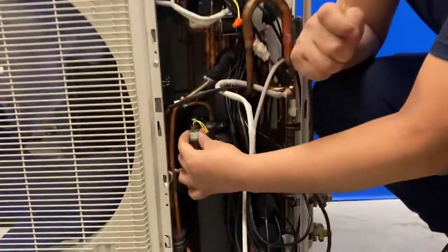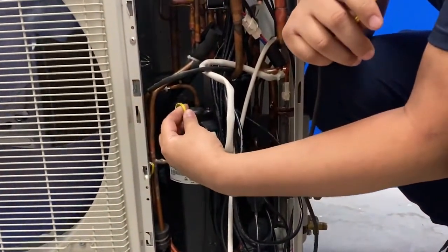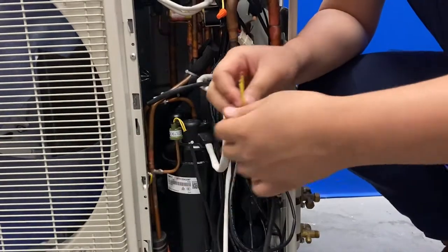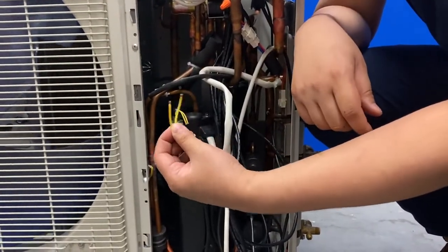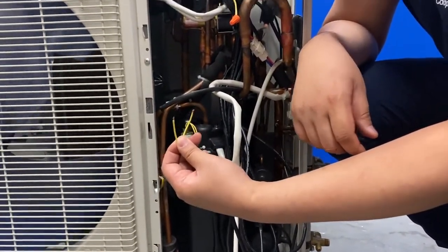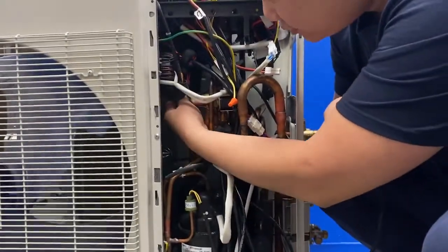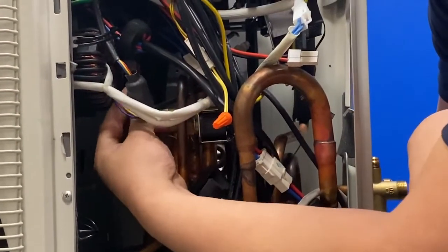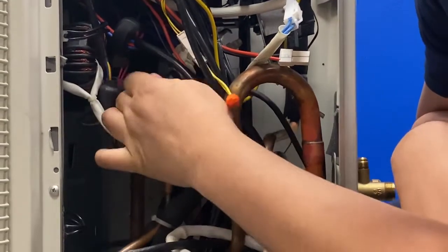First, I will locate the high pressure switch, indicated by 2 yellow wires. I will cut the connection going to the board and check for continuity. Then, I would locate the low pressure switch, indicated with 2 red wires, and then I will repeat the process.